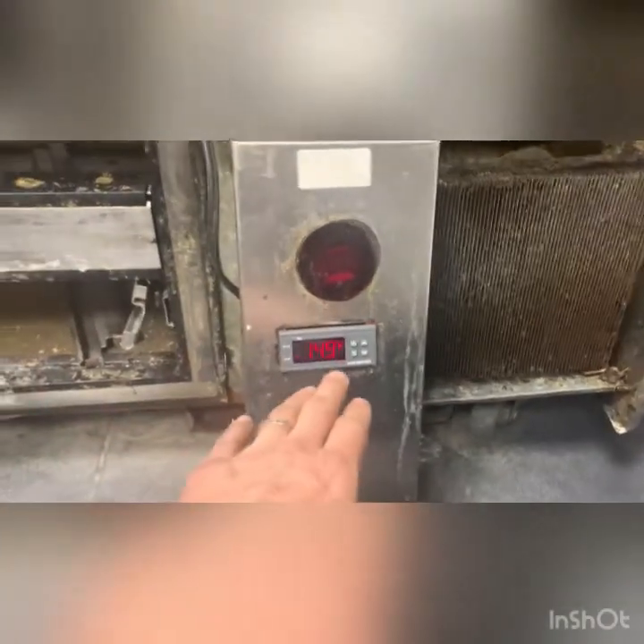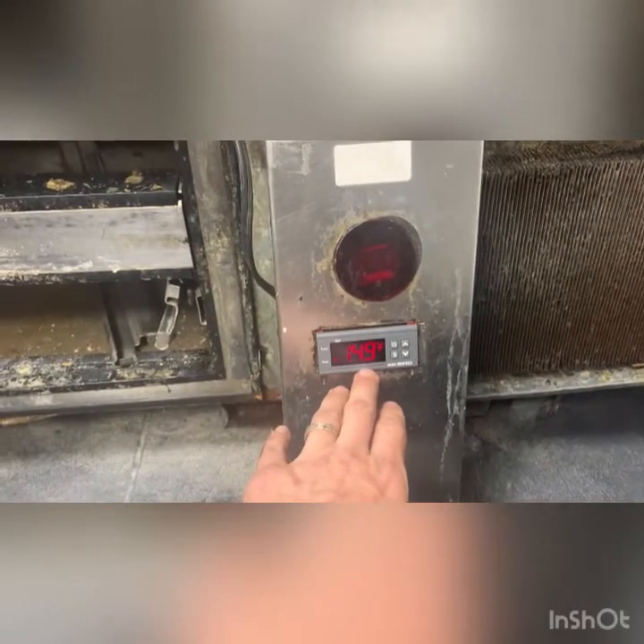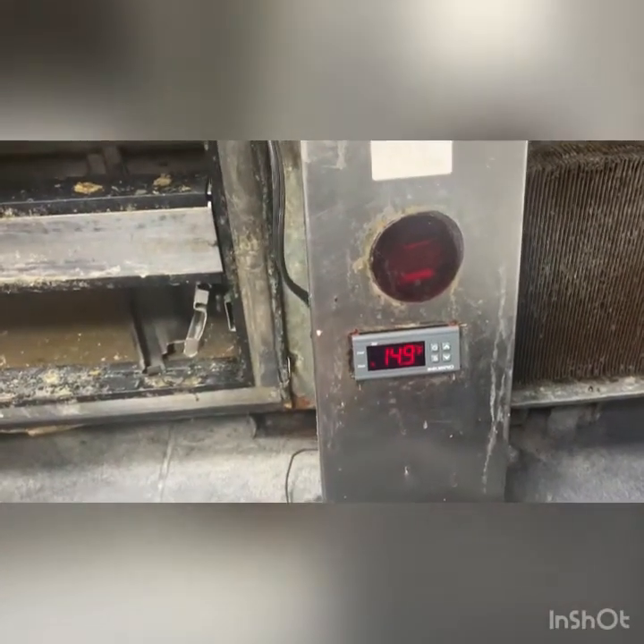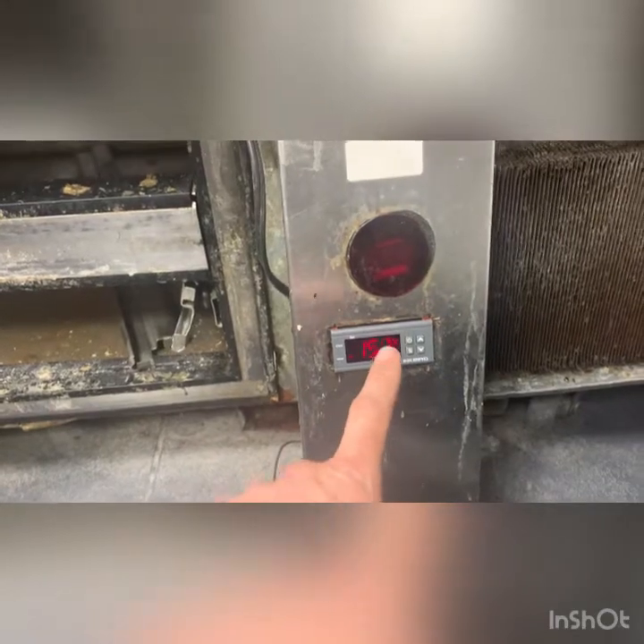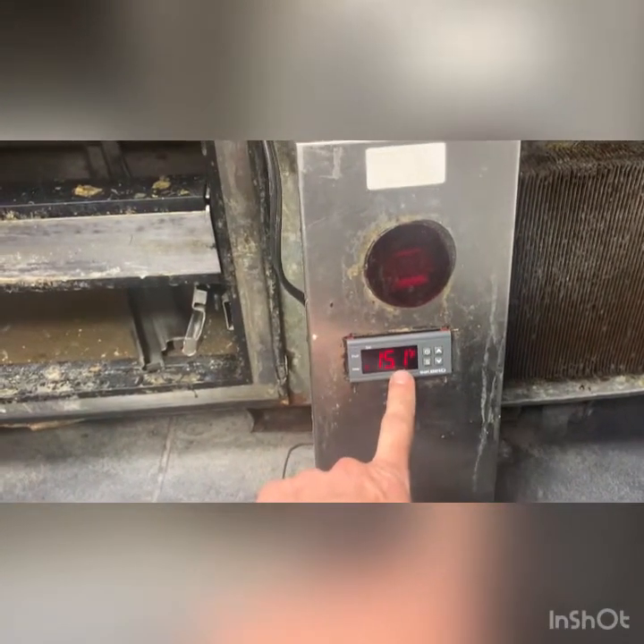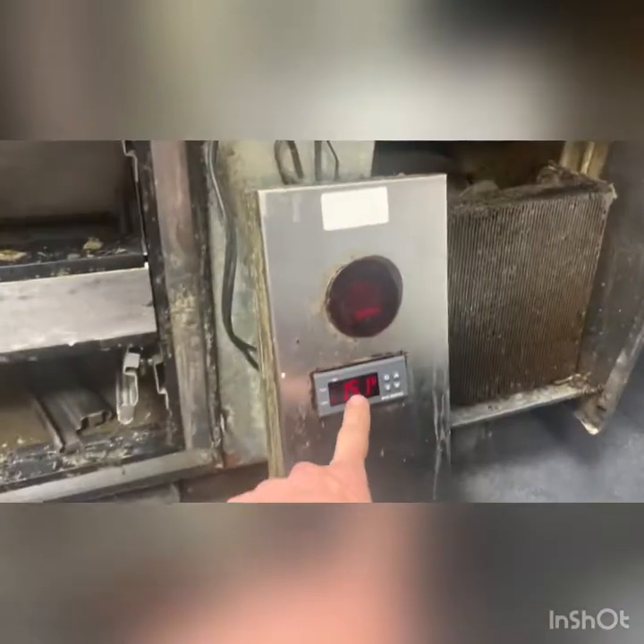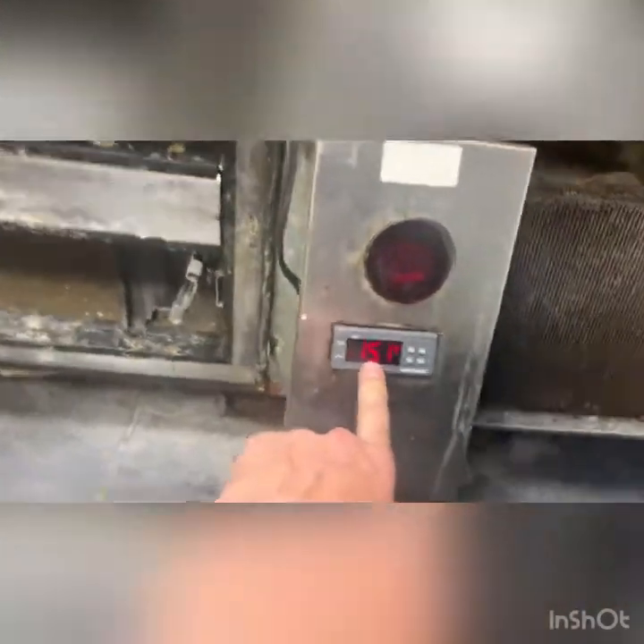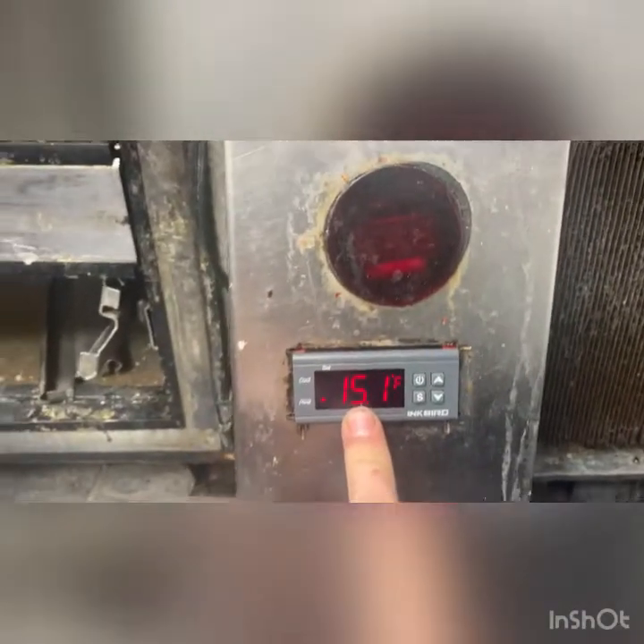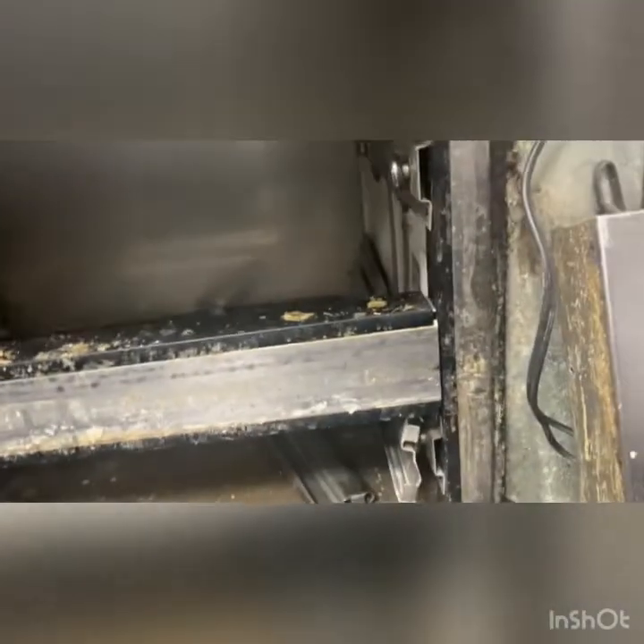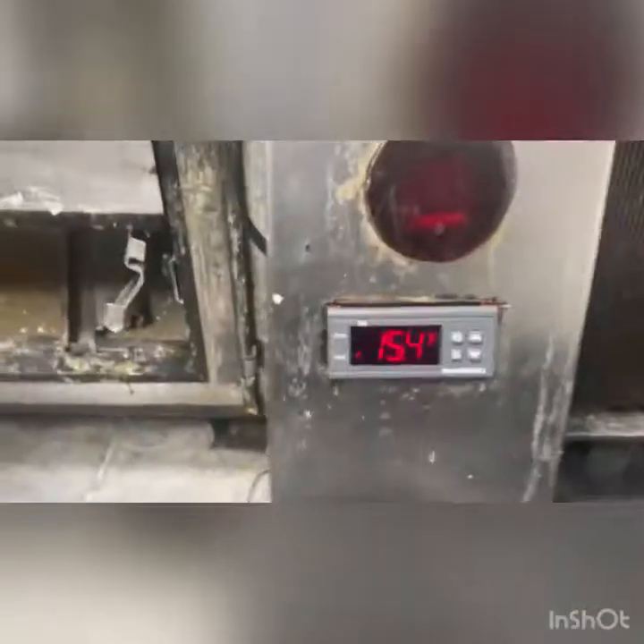So, powered back on, we're reading 15 degrees. This temperature sensor is in the coil. It is not in the cabinet. I'm going to go to a quieter place and I'll explain the science of that. Right now the evaporator fans are running. So our fans are running, but it's a ball of ice behind there.